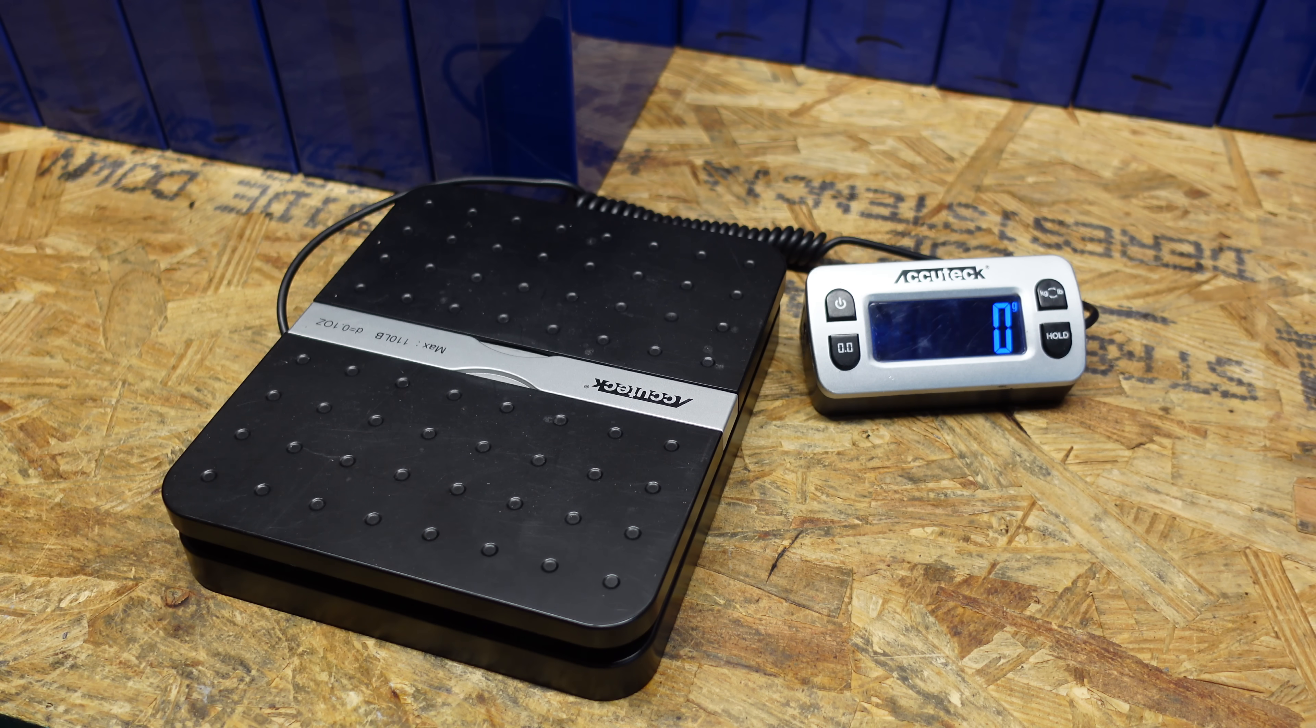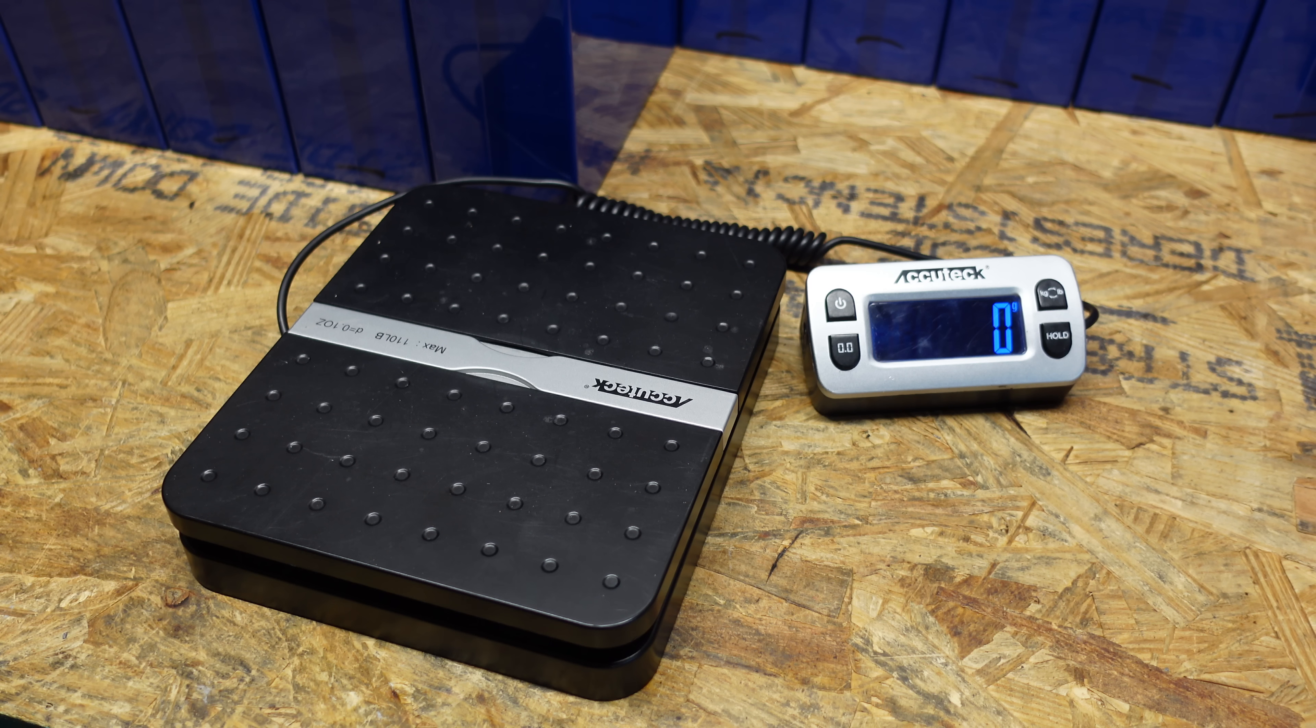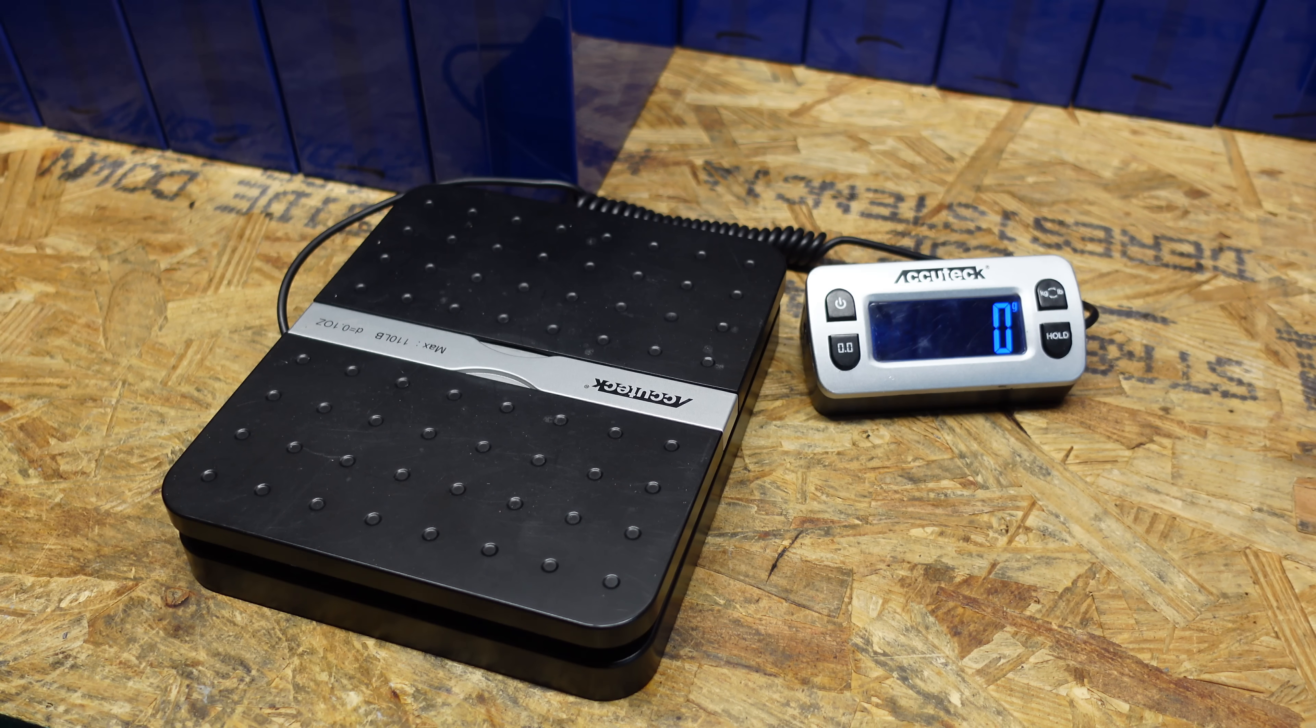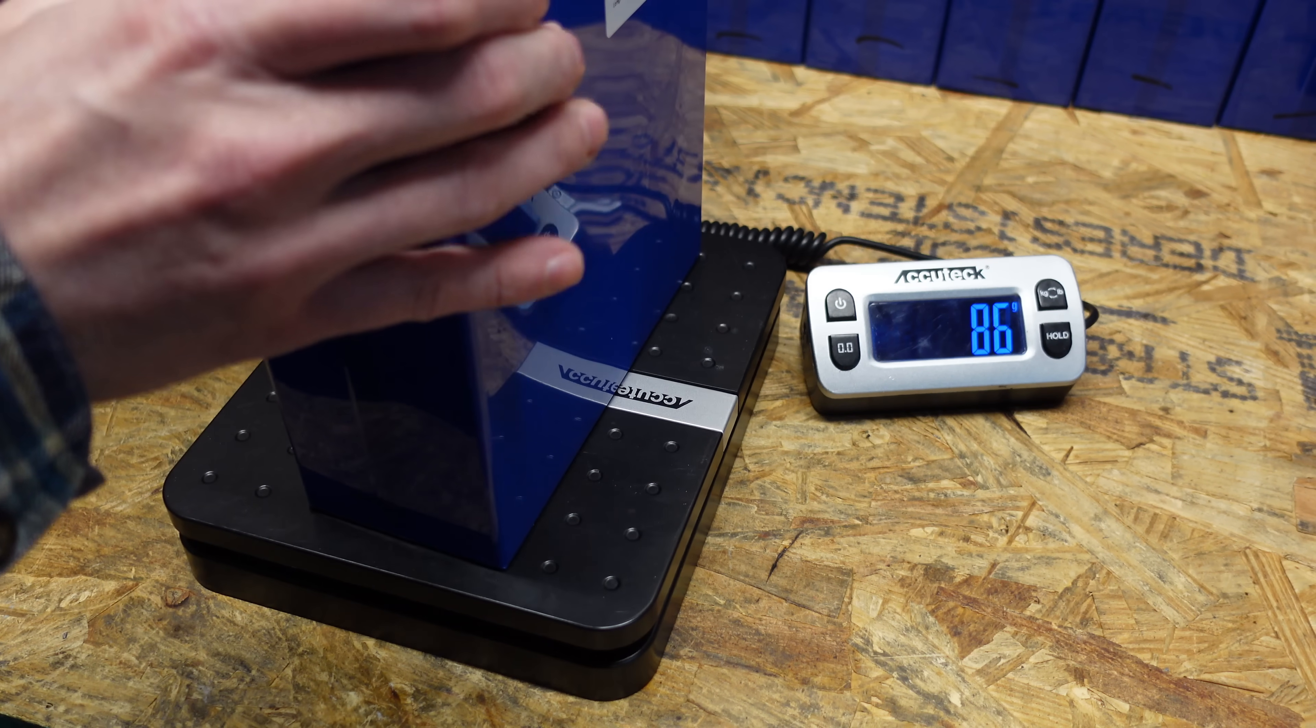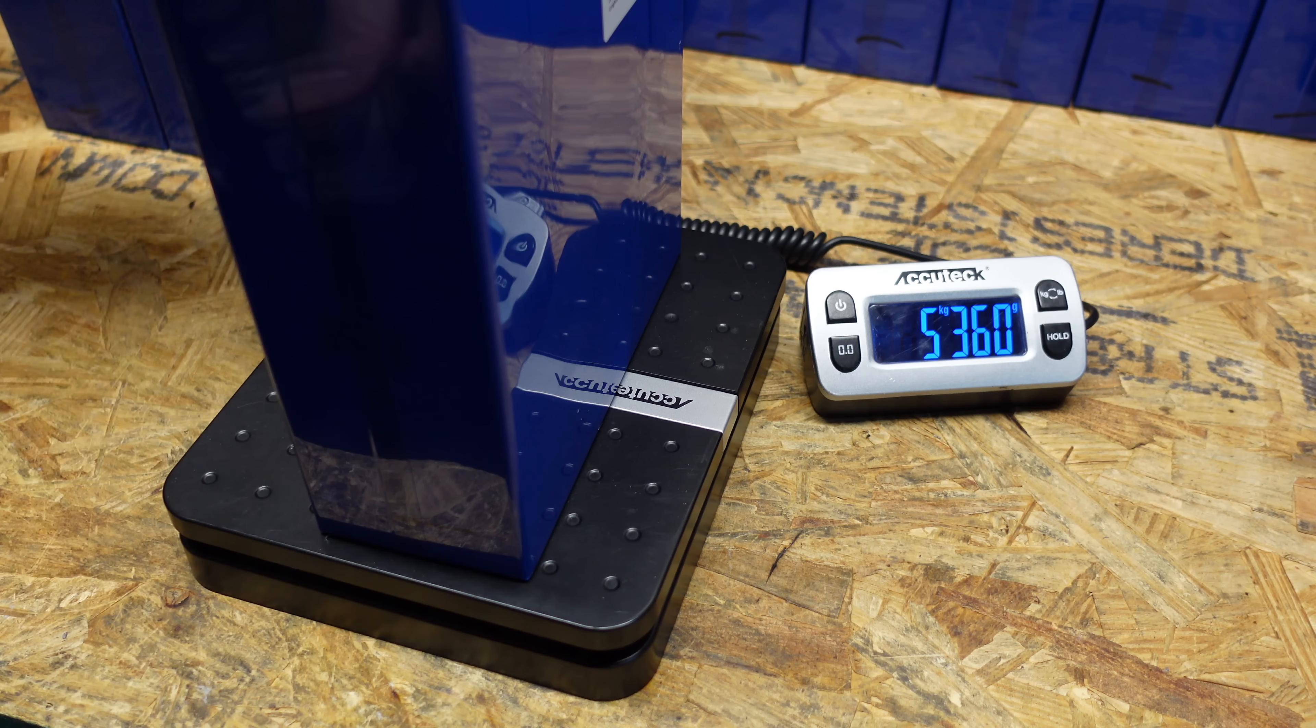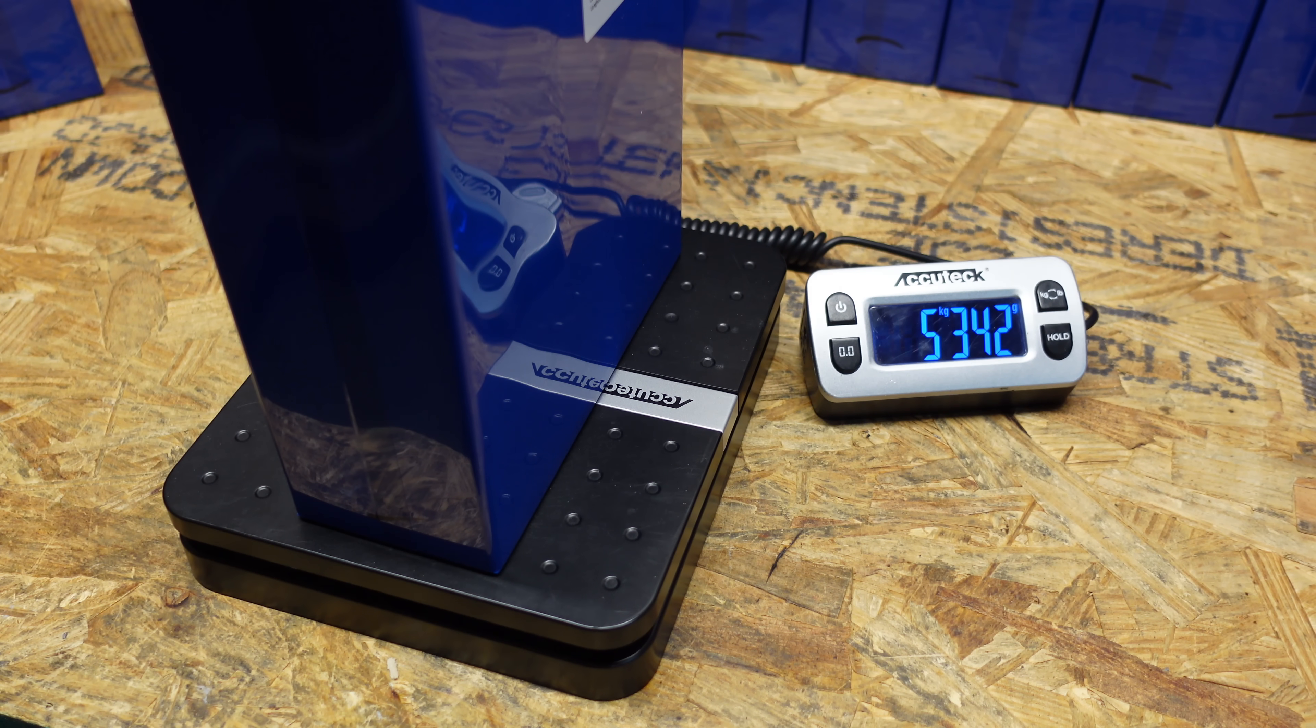All right, so one thing I want to do is weigh a couple of these and make sure the weight is in line with the specifications. These cells should weigh 5,220 grams, plus or minus 200 grams. I'm just going to grab a few at random here. 5,340, 5,360, 5,354, 5,342.